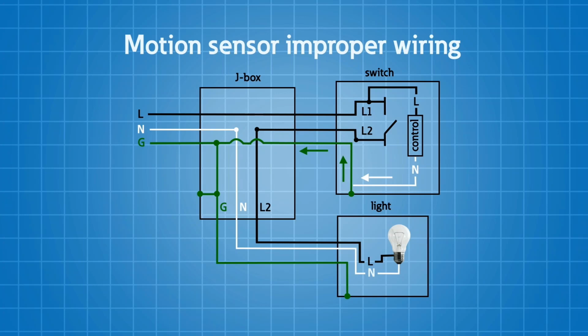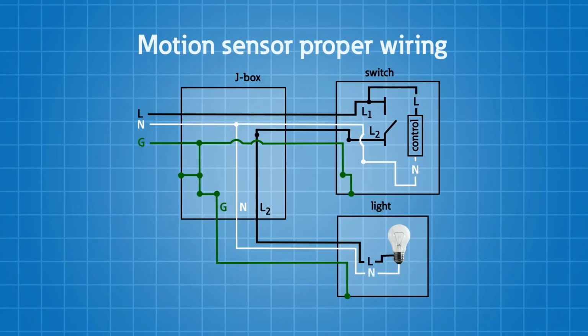And based upon the definition that we just created and just talked about, that would be current flowing on the equipment grounding conductor that's not because of a faulted condition. That would be what we call objectionable current. And that is not permitted by the National Electrical Code. So changes have occurred over the last few cycles, 1, to prohibit the use of those products, and 2, to require the pulling of a neutral at those switch locations.